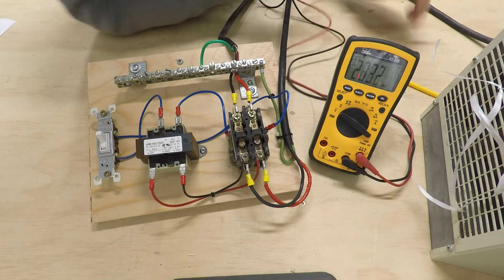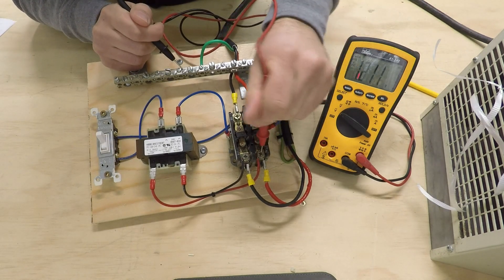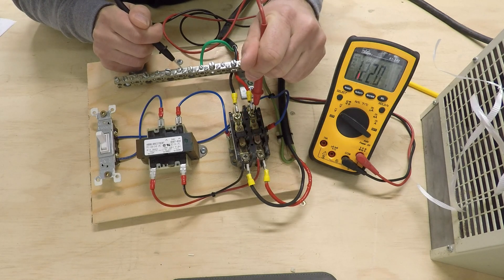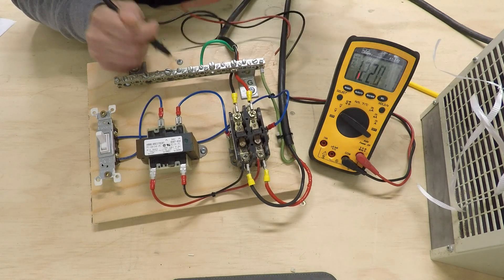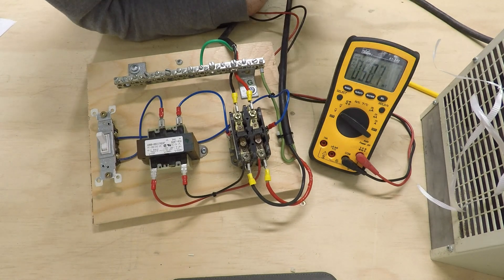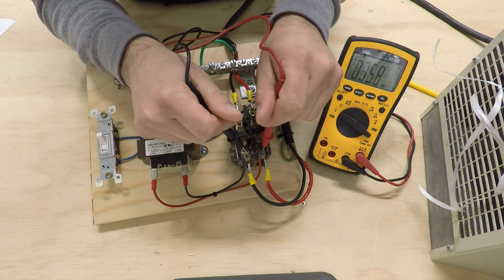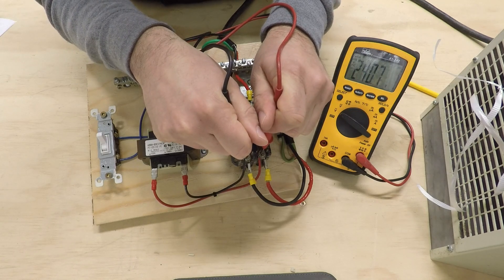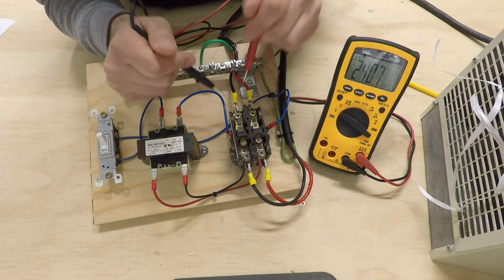So that's kind of strange because you measured the same 120 on both sides at the top. You're measuring it on both sides on the bottom. Then why isn't the fan turning on? Well, the issue is, is that you're actually not getting your 240 volts.